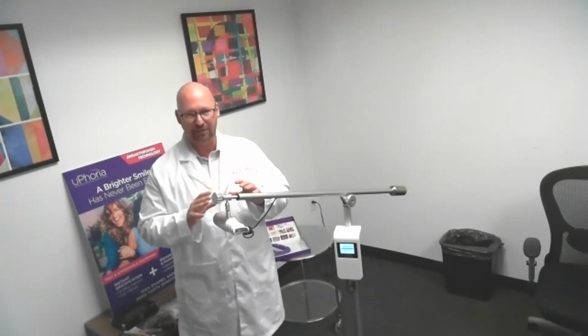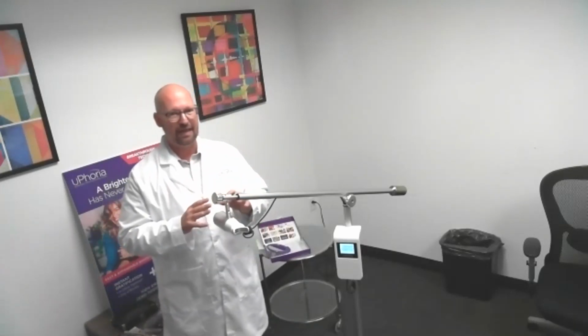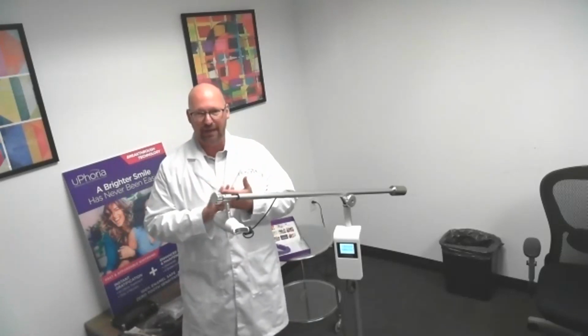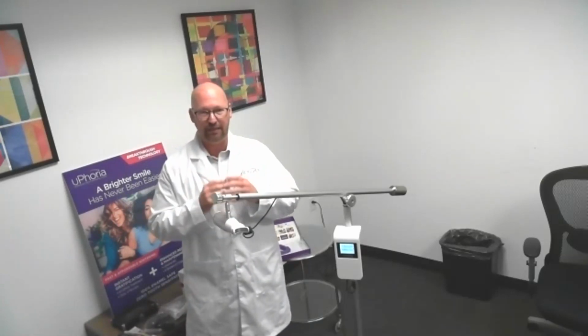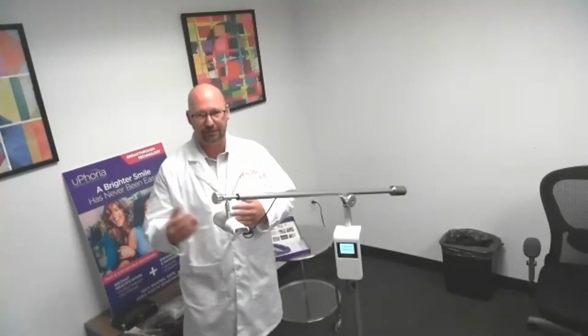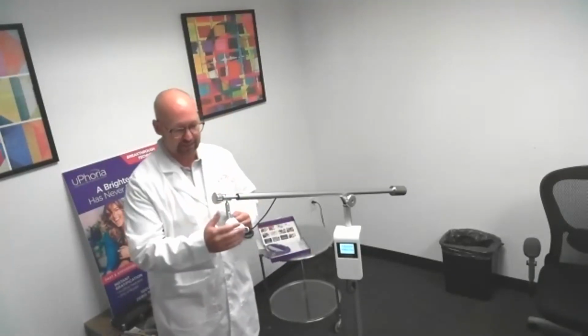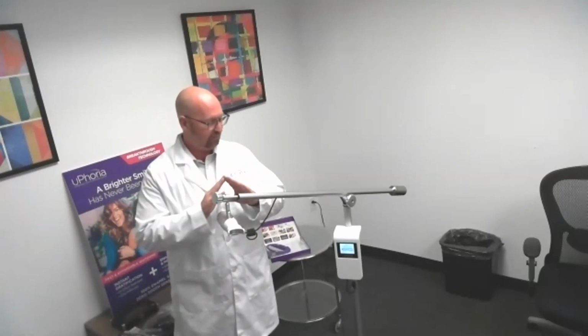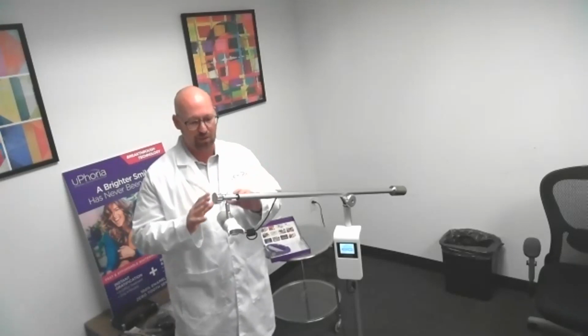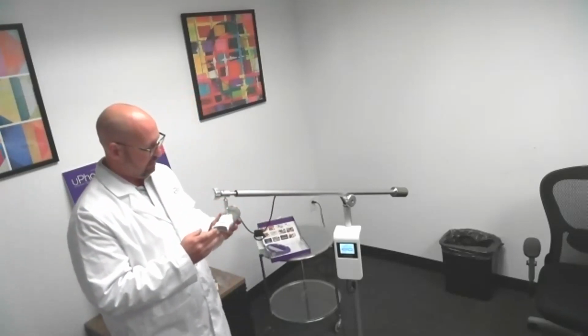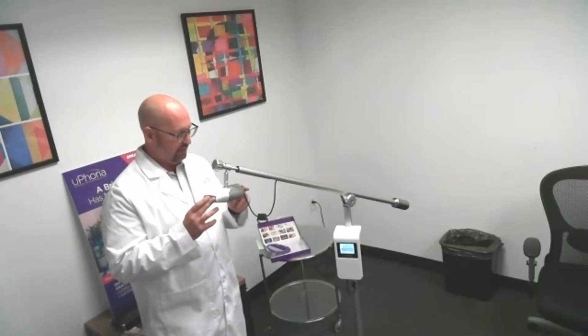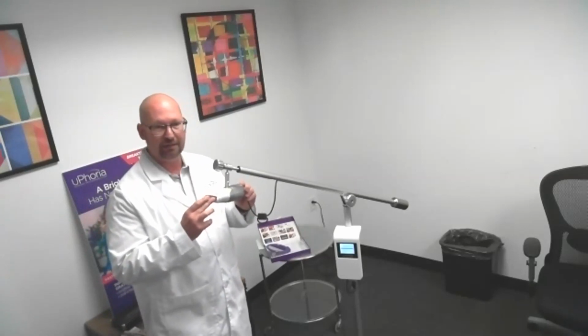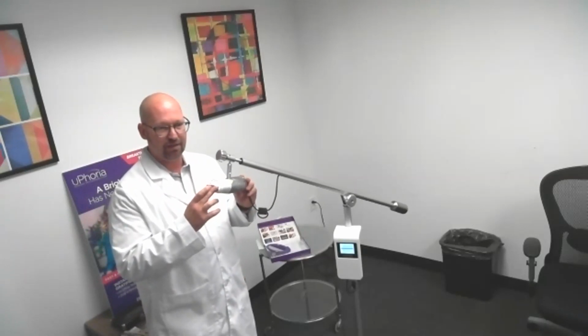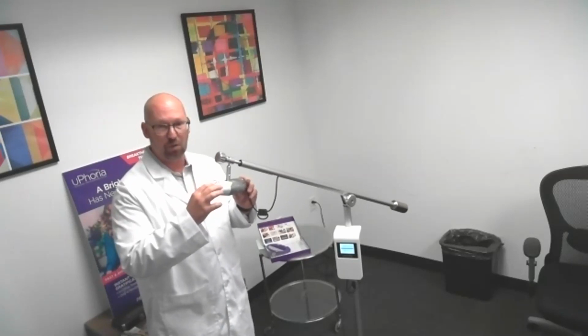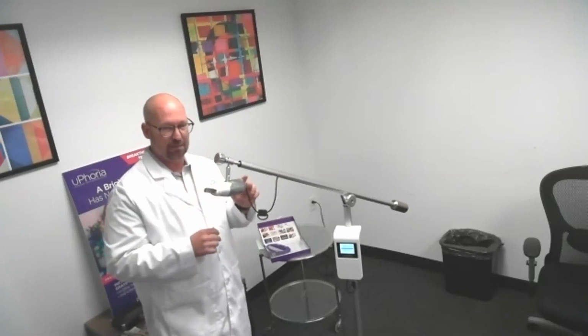A non-saturated foam pad will not allow the cavitation to go through to the foam pad, and it will not work. You need a fully saturated foam pad in order for the cavitation and the ultrasonic energy to actually get into the foam pad. And 3, and probably one of the most important things, anything I'm saying, this is the most important thing: when you have the ultrasonic unit up to the patient's teeth, there might be an inclination to push on the back of the ultrasonic unit, to where then you'll hear more hissing because more liquid is actually getting behind the metal horn.